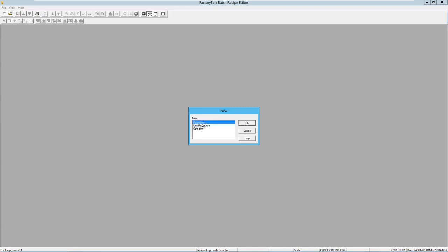Finally, I then have a procedure, and the procedure has a sequence of unit procedures, and these can be one after the other, and they can also be in parallel. A procedure can contain unit procedures for multiple units. So the procedure in our example could contain 2 unit procedures, one for each of our premixers running in parallel, making material in those 2 premixers in parallel, and then transferring them into our single reactor, where it then moves to just running the unit procedure for the reactor.